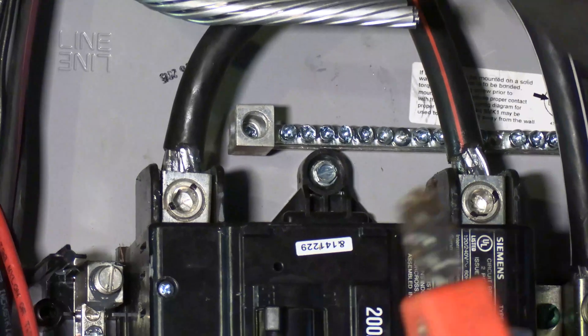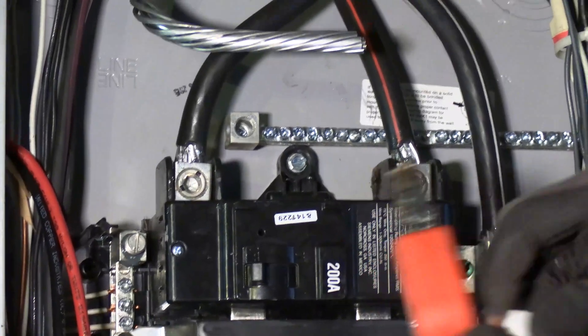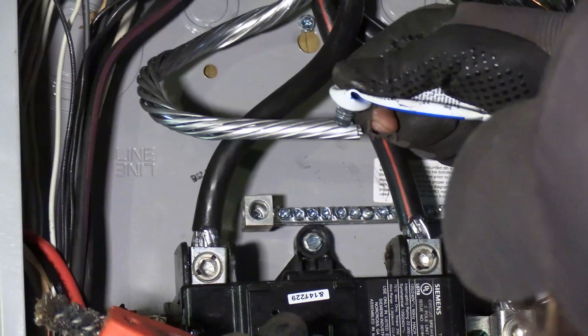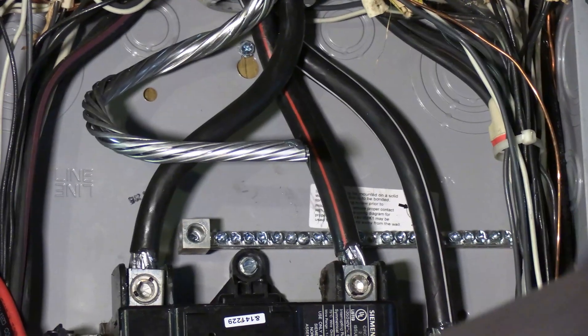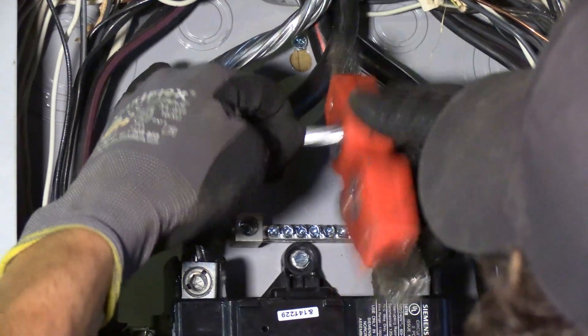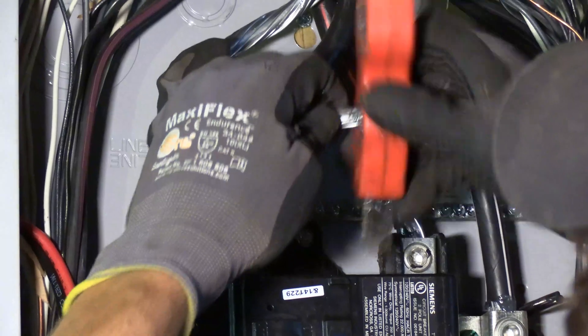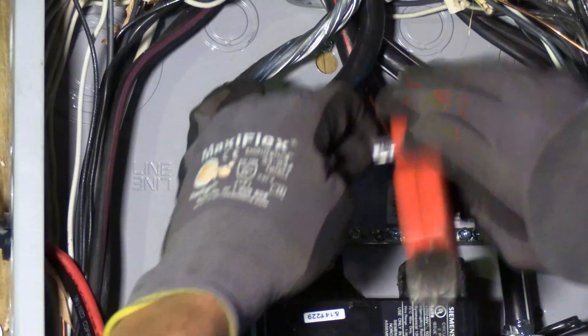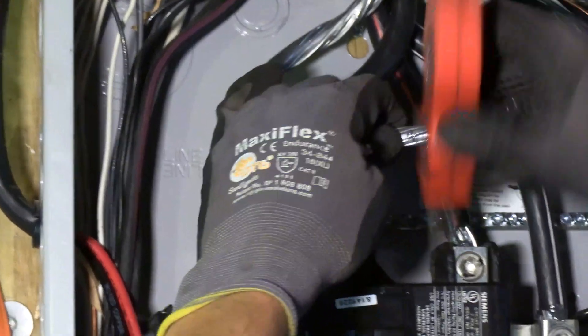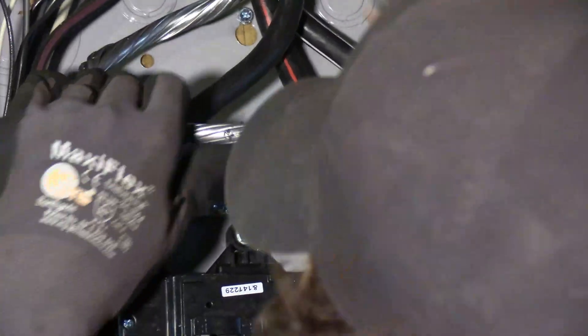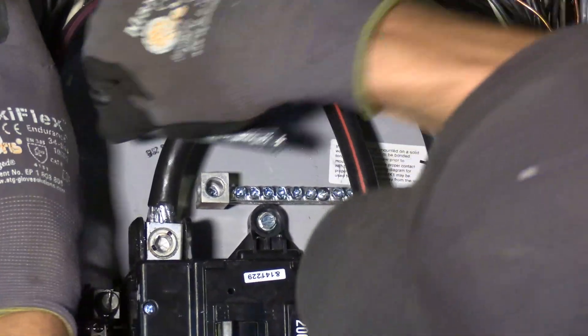Now when you're terminating aluminum conductors, one thing you need to know is that special measures are required. This is a Noalox. It's a no aluminum oxidation. It's an anti-oxidation compound and it's required to be brushed into aluminum conductors. I'm just going to put it on the end, brush it into the point, wire brush it into the point of termination and that's going to prevent it from getting that white chalky high resistance oxidation.